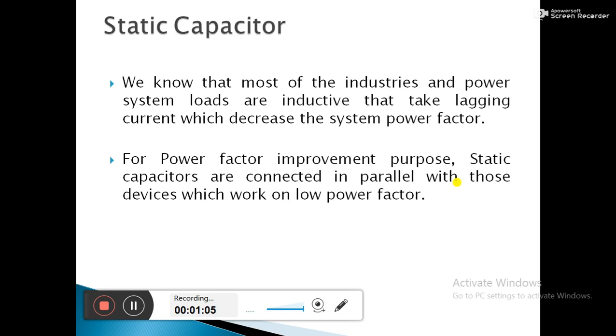The first method is static capacitor. We know that most of the industries and power system loads are inductive, and they take lagging current which decreases the system power factor. All residential and industrial loads are inductive in nature, so they take lagging current, which leads to a lagging power factor. That is why we need to improve the power factor by using the static capacitor. For power factor improvement, static capacitors are connected in parallel with those devices which work on low power factor.